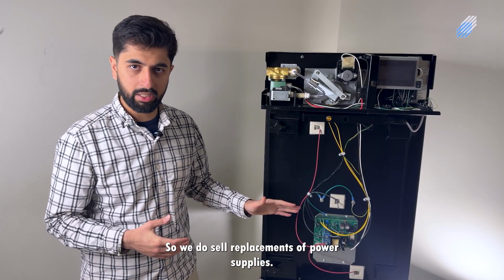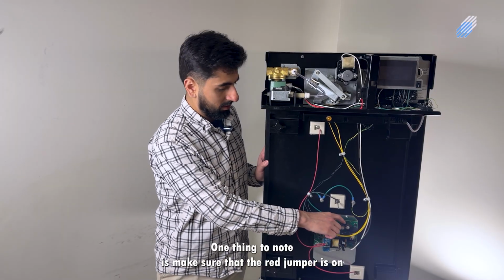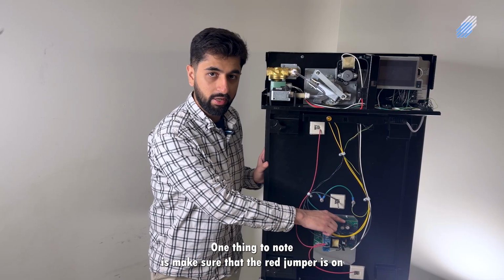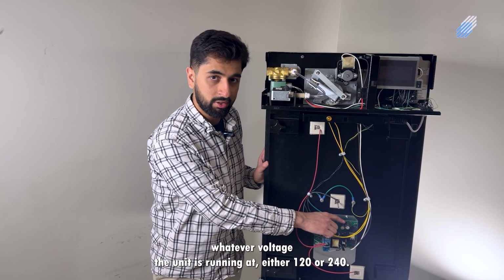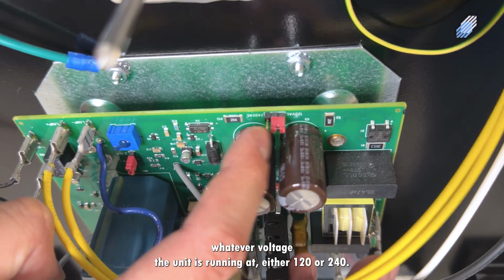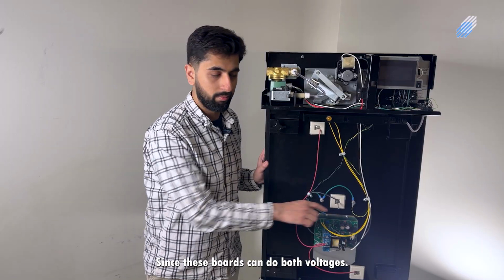And so we do sell replacements of power supplies. One thing to note is to make sure that the red jumper is on whatever voltage the unit is running at, either 120 or 240, since these boards can do both voltages.